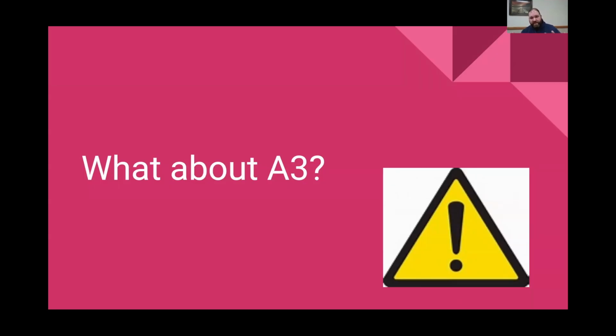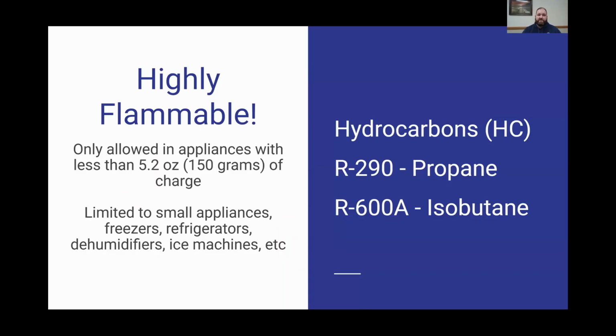Now, a lot of people are saying, well, this new refrigerant is propane based. Propane is a refrigerant. It is an A3 refrigerant. So A3 refrigerants are highly flammable. We are allowed to use A3 refrigerants, specifically two listed over here on the right. R290, which is propane. It is pure propane. The stuff in your grill tank is not pure propane, so they recommend not using it. You could lose 3 to 6% capacity of the system. The other is R600A, which is isobutane. Both of these are naturally occurring hydrocarbons.